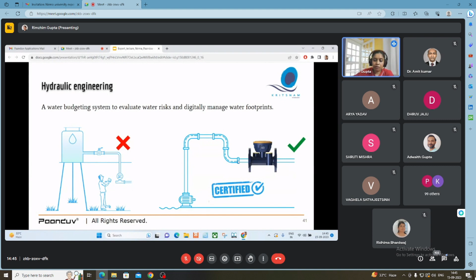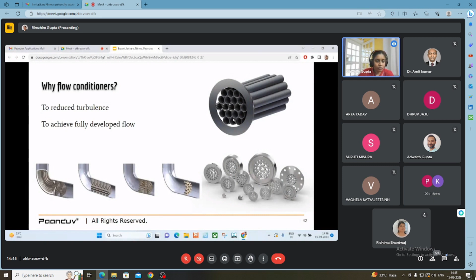The problem with these flow meters is that they are accurate only when provided with a fully developed flow. If there is existence of air in the water flow, the reading will not be accurate. So to maintain the accuracy of these flow meters, turbulence should be minimized and it should be a fully developed flow. So we used a strategy called a flow conditioner, which is used to reduce the overall turbulence in the system and to achieve fully developed flow.